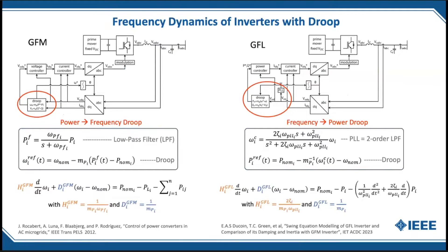Let me look at some forms of stability, starting with frequency and the grid-forming inverter. This is an inverter that presents as a voltage source where the frequency and amplitude depend on the real and reactive power flows. The measured power influences the frequency through a low-pass filter, introducing dynamics. The difference between the power and its reference value is used to droop the frequency. This gives a coupling that looks just like a swing equation for a synchronous machine, with terms that look like inertia and damping depending on the droop characteristics.